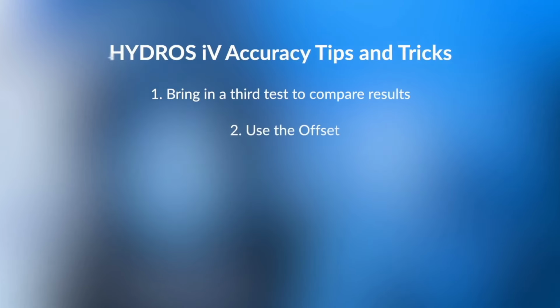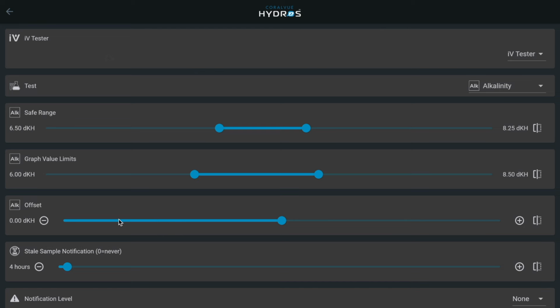Talking about differences, one of the biggest reasons we have offsets put into the software is if you want to believe your trusty test kit is the gold standard and this is what you want to go by, by all means, use your offset, bring it up or down to where you feel like it really is. That's why we put that in there. Just make sure that you always question that reference, that there is a possibility that that reference test is not right.